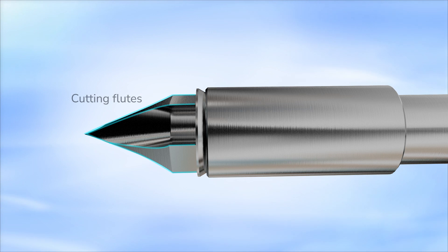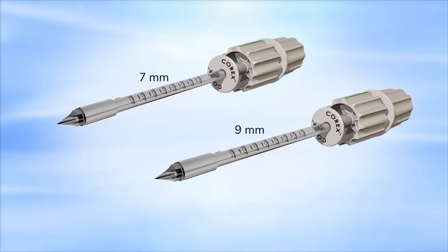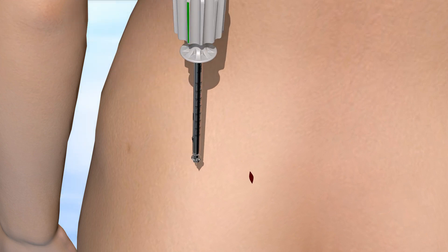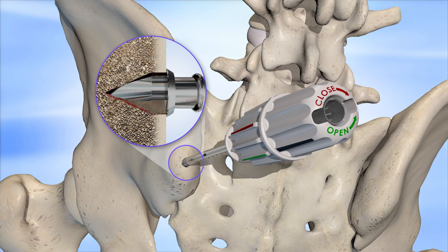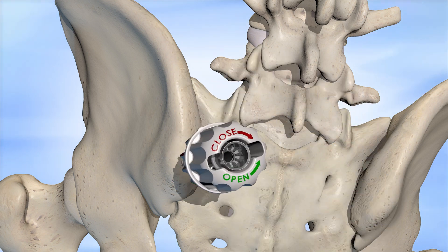The Corex Minimally Invasive Bone Harvester is engineered to help you consistently deliver optimal patient outcomes with percutaneous autologous cancellous bone graft harvesting. Unlike most other devices, the Corex device provides an integrated means of breaching the subcutaneous cortex using a removable trocar tip. Corex is available in seven millimeter and nine millimeter diameters. The device is inserted through a single stab incision through the subcutaneous tissue to the periosteum and then advanced under manual control. The trocar tip has a safety flange that minimizes the risk for excessive penetration beyond the intended cortical opening.